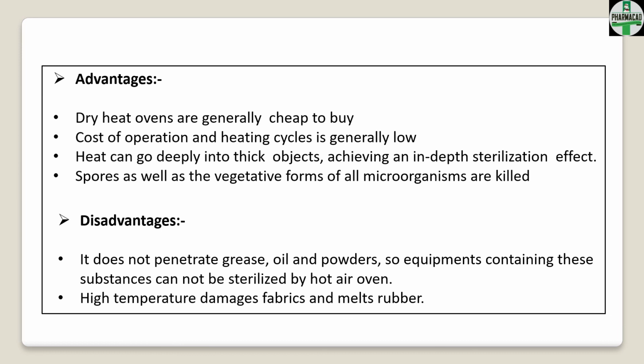It has a few disadvantages, like it cannot operate on wet objects and on materials that will melt, catch fire, or change form when exposed to high temperature. So it does not penetrate inside grease, oil and powders. So equipment containing these substances cannot be sterilized by a hot air oven. High temperature damages fabrics and melts rubber. So we have to avoid using these objects.